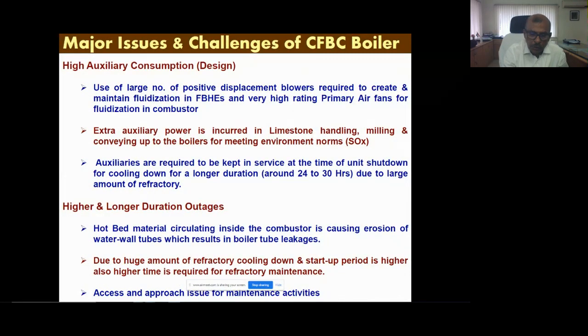The major issue we have just discussed is the auxiliary power consumption, and that is mainly because of the number of blowers for creating fluidization in the different fluidized bed heat exchangers, and the primary air fan operating at around 225 millibars for fluidization in the combustor. This is a major contributor to auxiliary consumption. Extra auxiliary power is also needed, as I already said, for lime handling, milling and conveying to the boilers to meet environmental norms. But if we now consider the new environmental norms with a PF boiler also going for an FGD plant, this may be comparable.